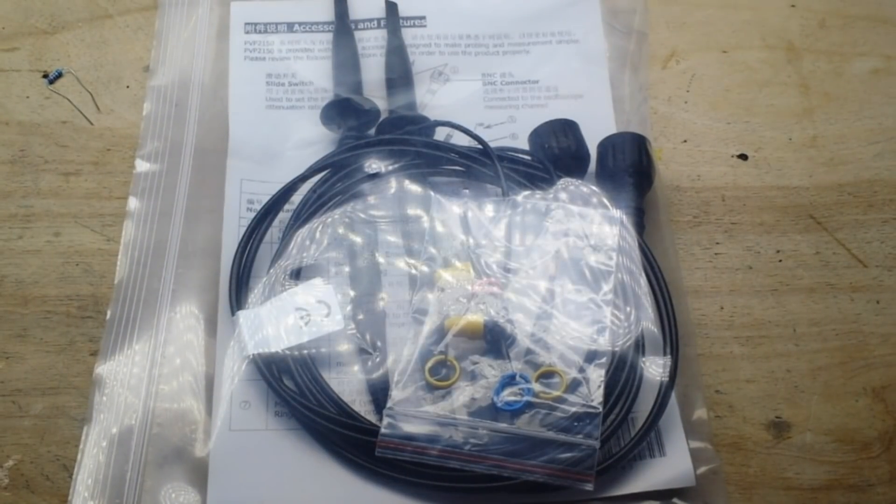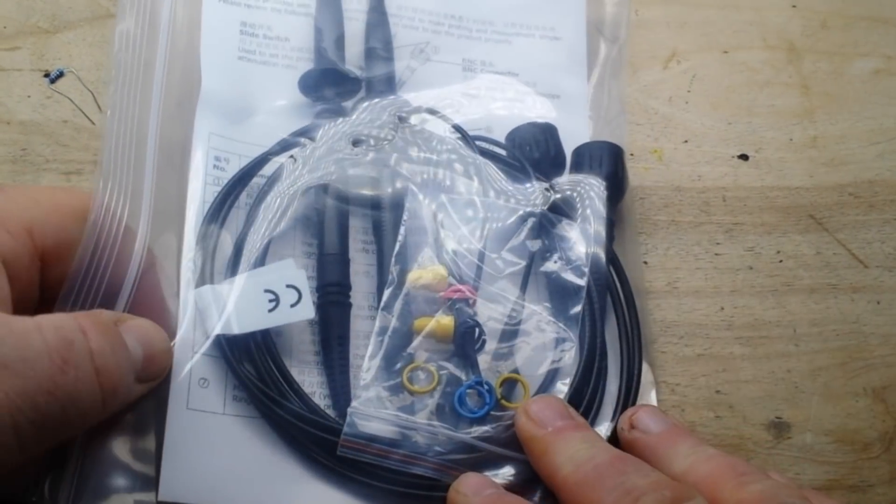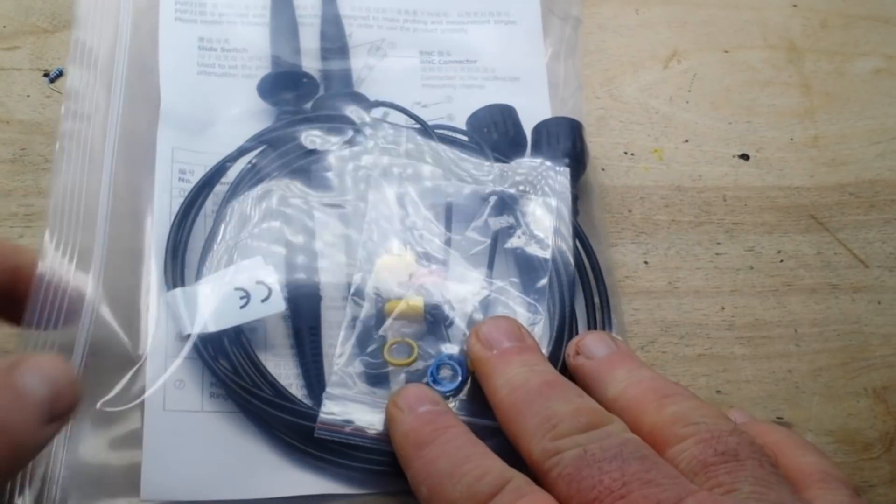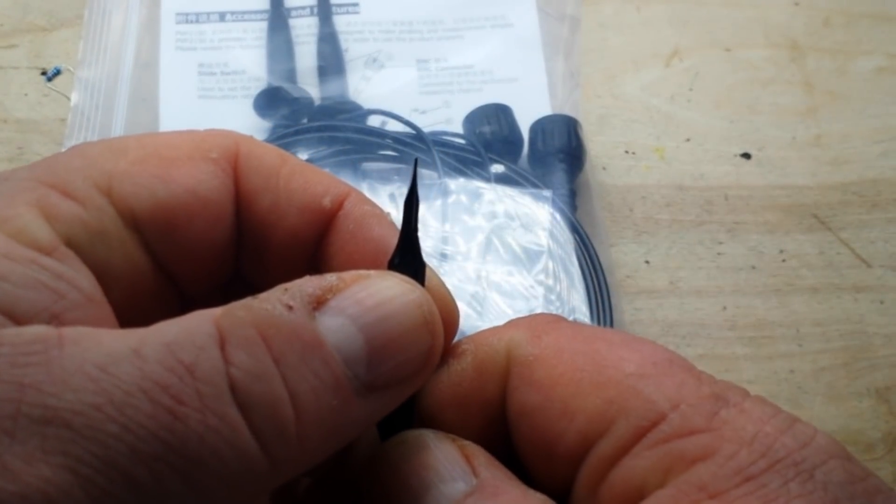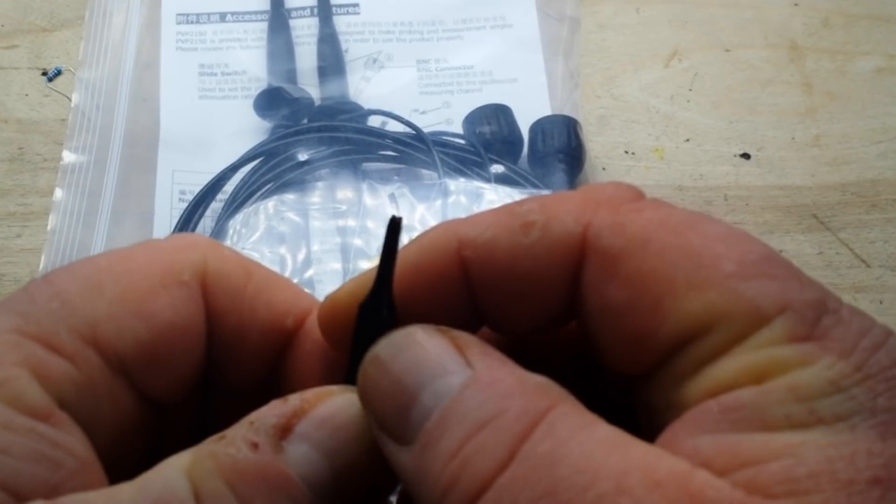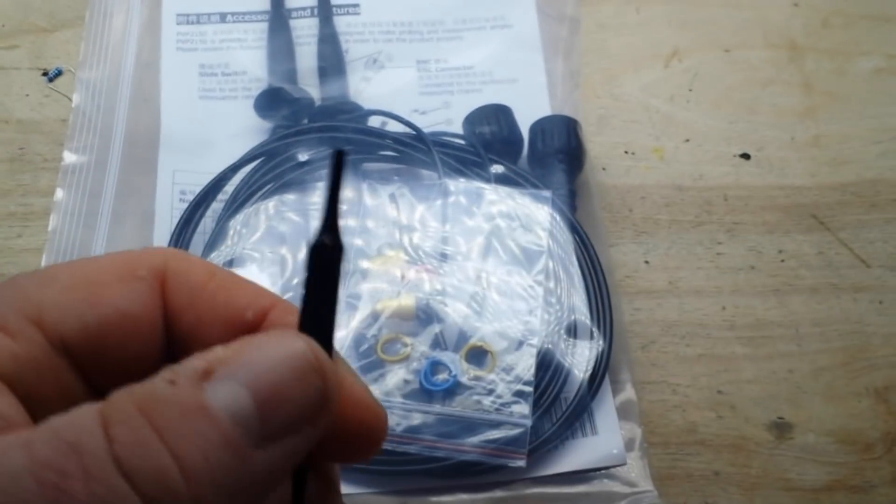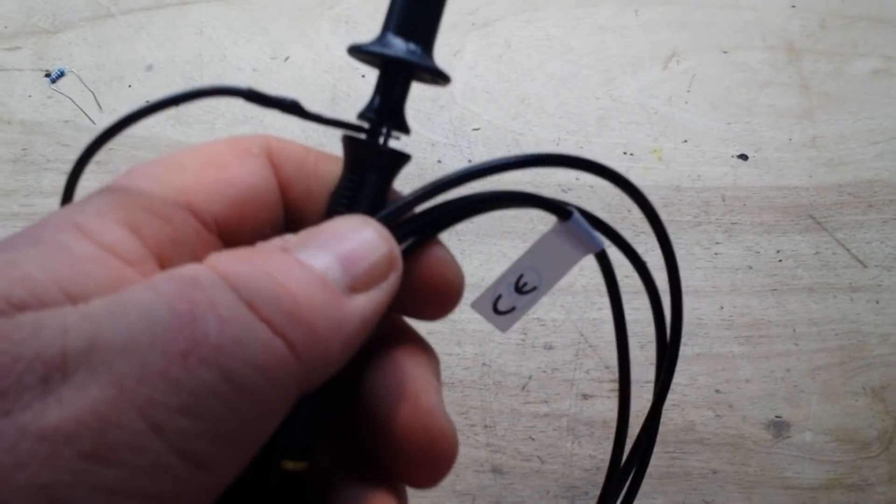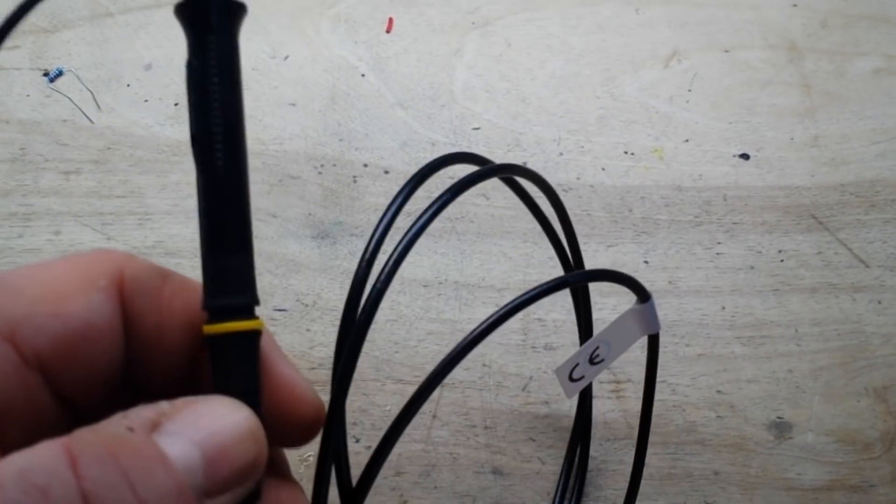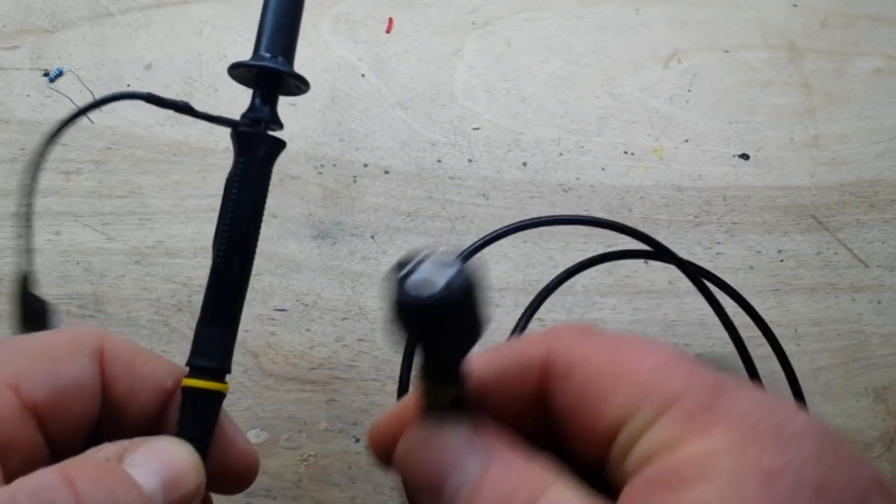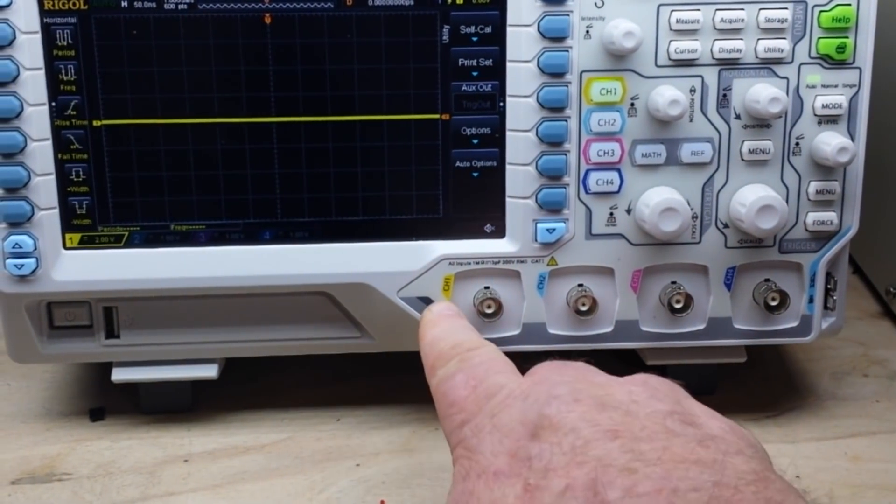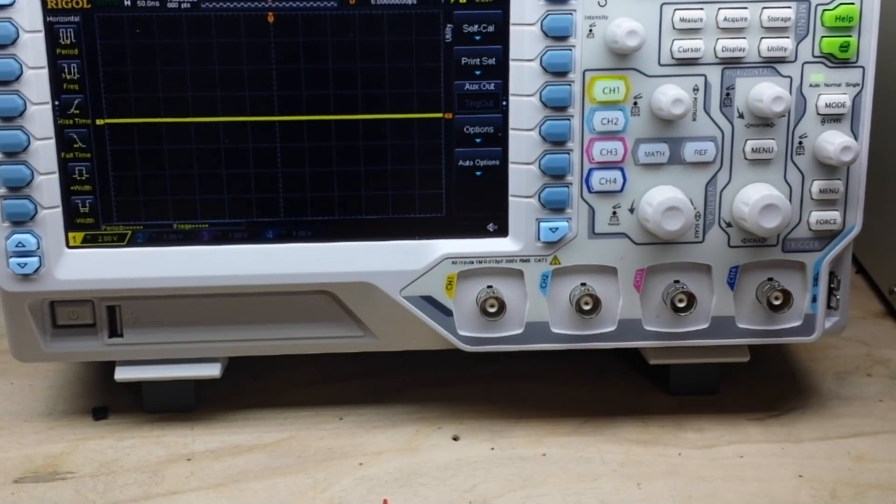So unpack your probes and inside the package here you're going to find one of these little adjustment tools. It has a flat blade on one end and sort of an inverted four-bladed thing on the other end. So we're going to need one of those. Then you're going to want to do this for each and every one of your probes. The first thing I would recommend doing is getting out those little colored discs, put one on the probe and one on the connection, same color, and then you're going to match that up to the colors that are on your scope.